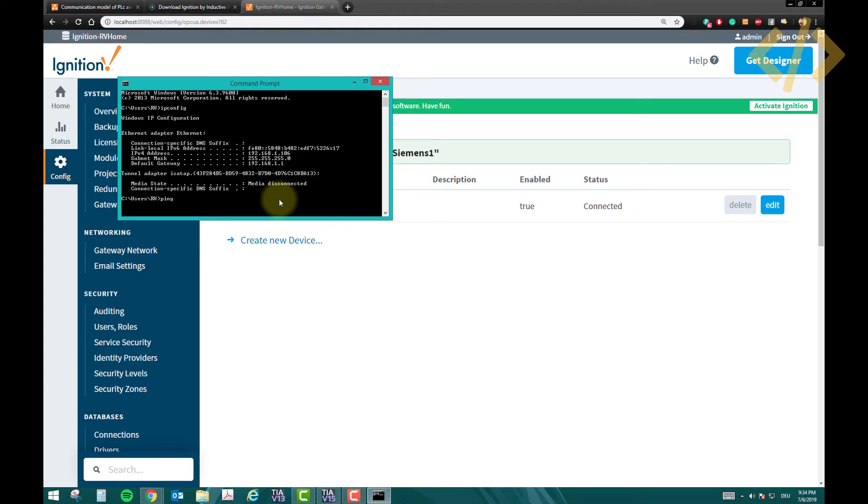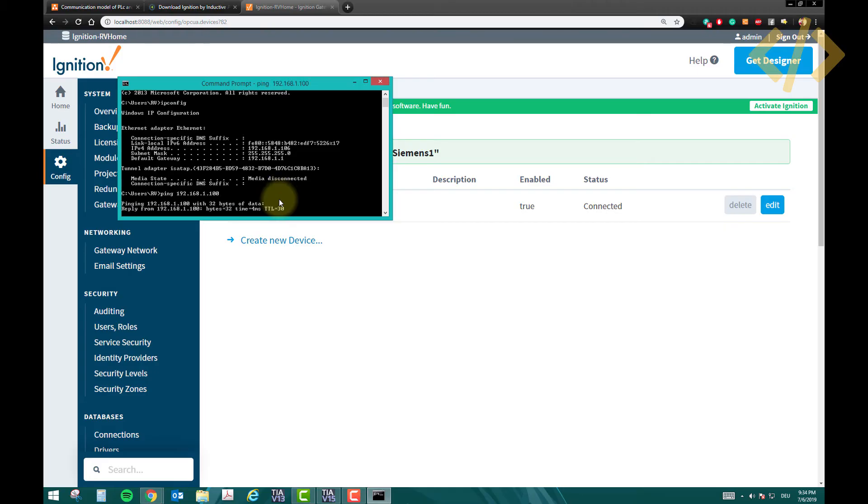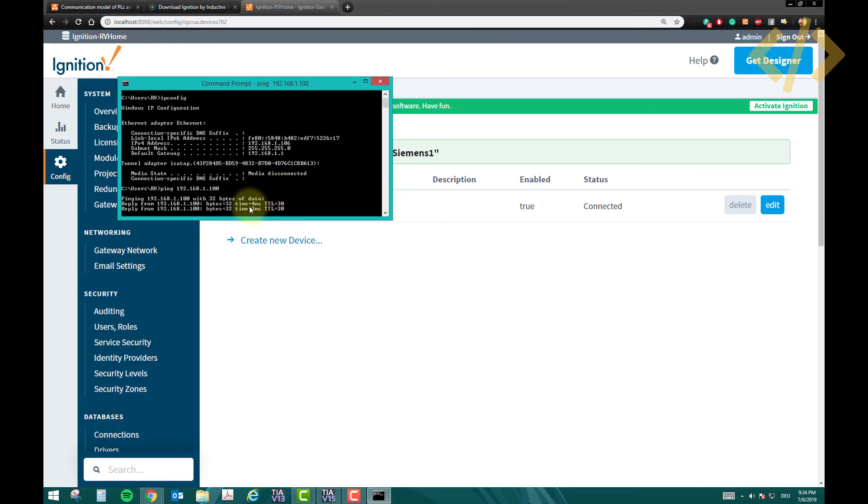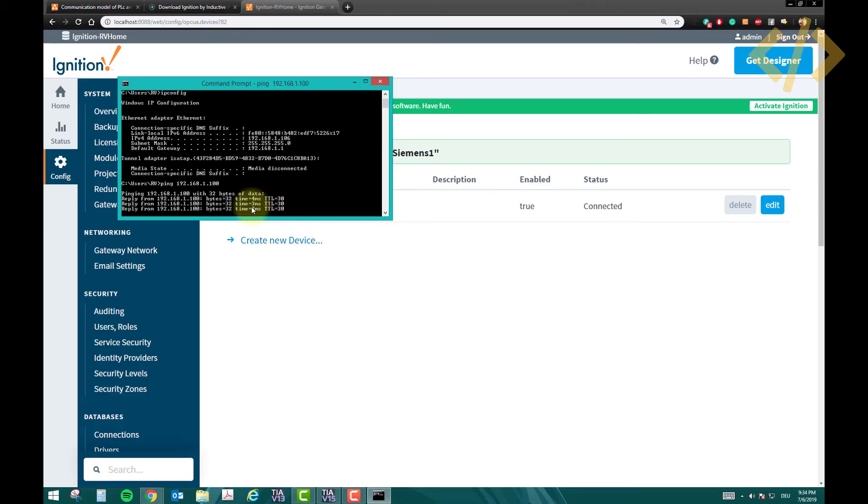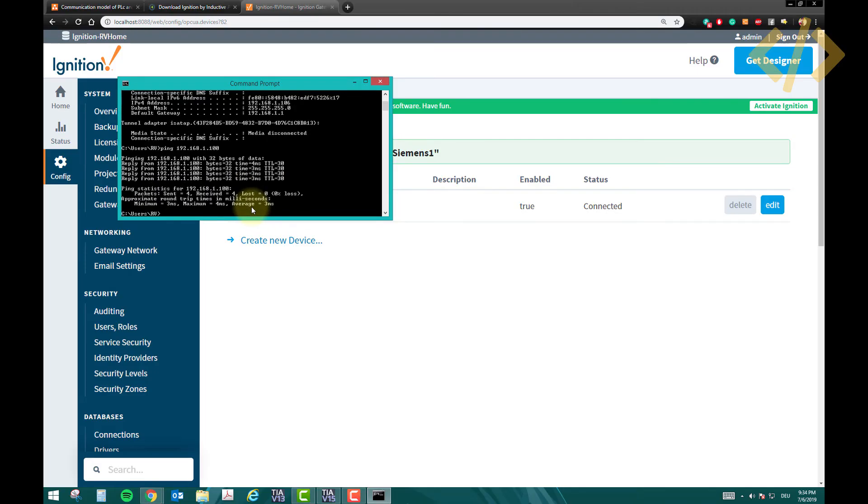So if I show you, if I ping my PLC, I will get a response. So my Ethernet card is communicating with my PLC, so it will say connected. If you can't see connected here, it means there is a disconnection or misconnection between your computer and the PLC.